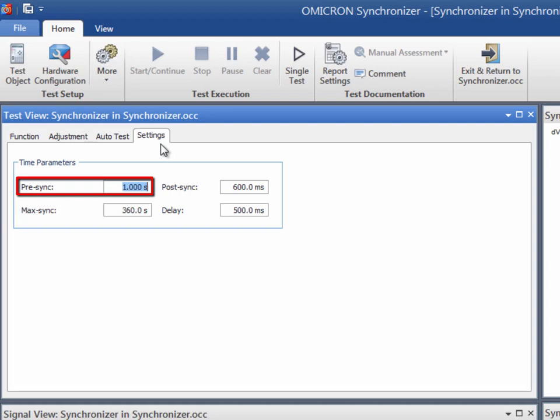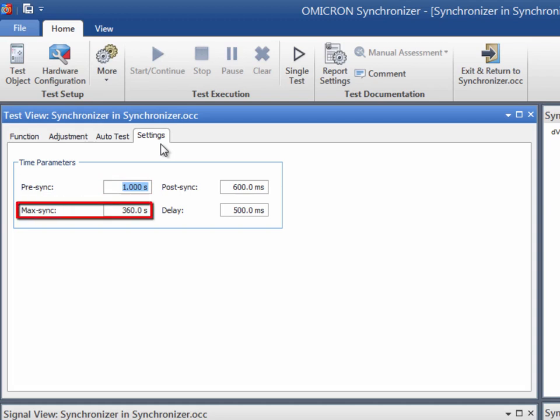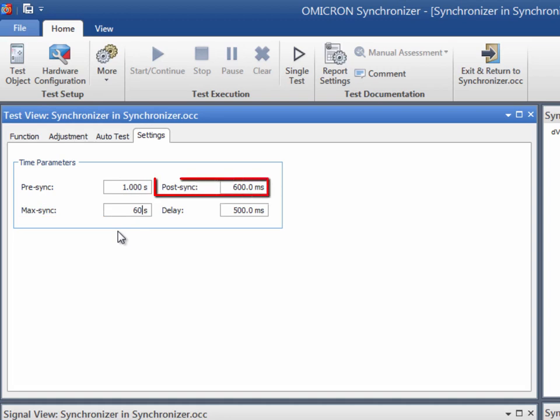At the end of the pre-synchronization time, the start signal is issued. The maximum synchronization time limits the amount of time for each test point. Only when the synchronization is achieved within this time can the test advance into the post-synchronization period. During this time period, the CMC test equipment continues to output voltages and sends the release command.